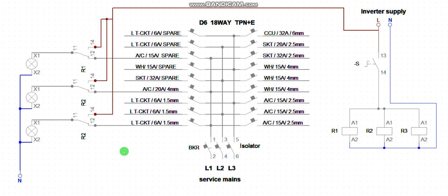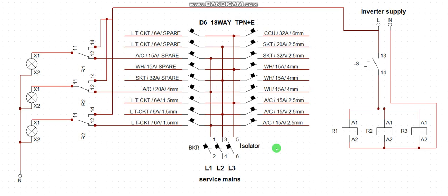So this is the ideal way to do your inverter incorporation so that the three-phase distribution or the genset, remember that some of the clients use three-phase generator, so that load balancing of the three-phase winding from the alternator must be maintained. Because if you make your alteration here by taking one of the phases to put on the lighting circuit, then the whole load is shared to the other two phases. This phase that is controlling the lighting circuit will have lesser load, while the other two phases will take higher load, thereby sending imbalance voltage and current carrying capacity to the distribution board, to the genset. And the winding of that genset, the lifespan will be at stake because the load is no longer balanced. So to maintain the balancing of this distribution board, this is what you need to do.